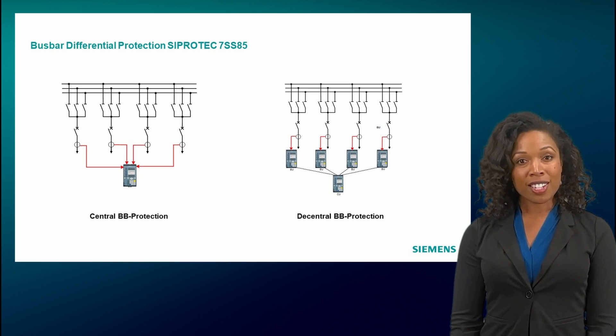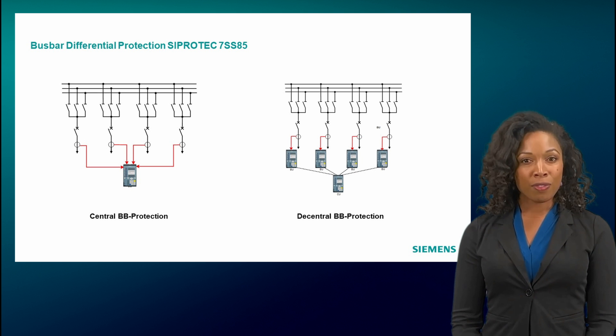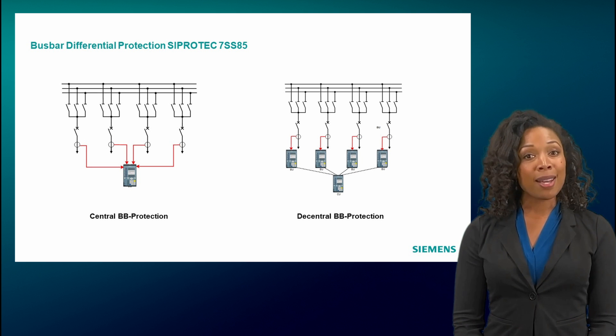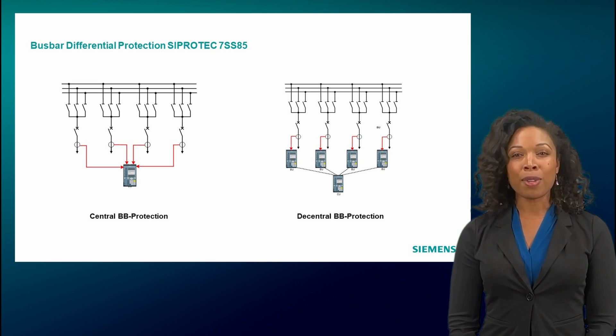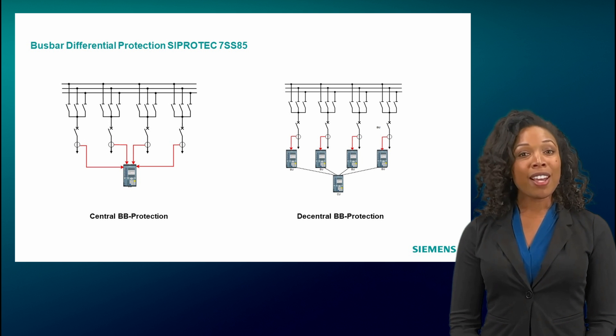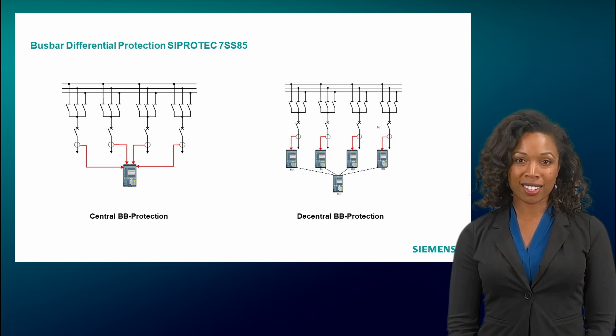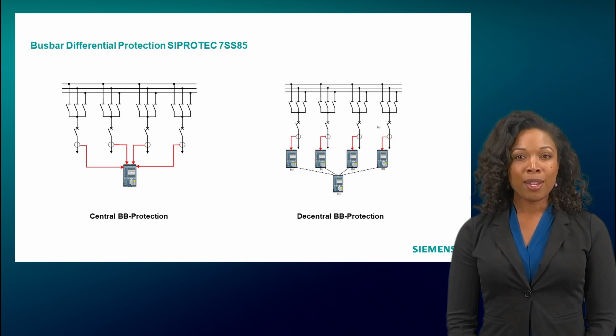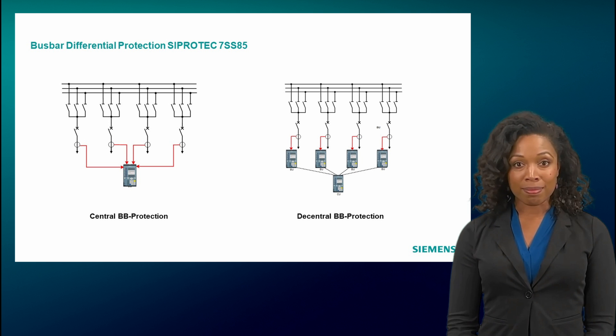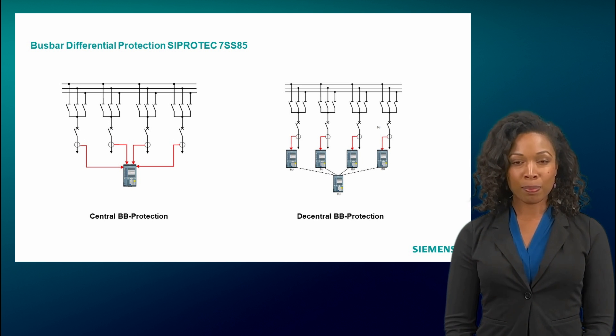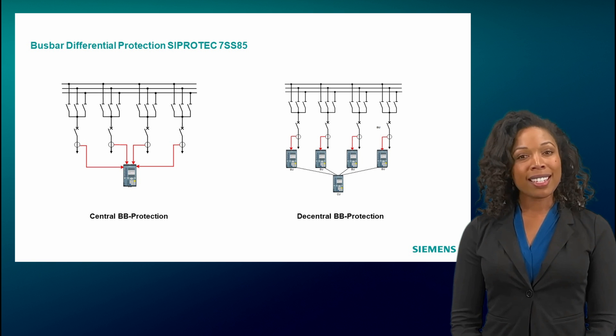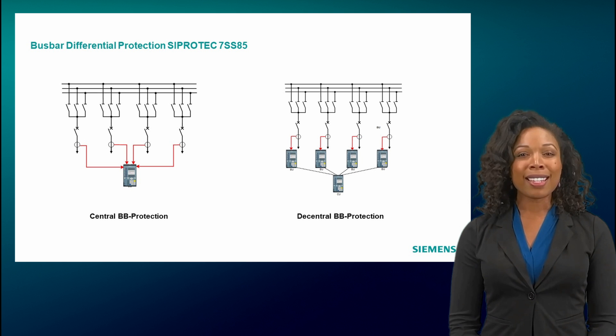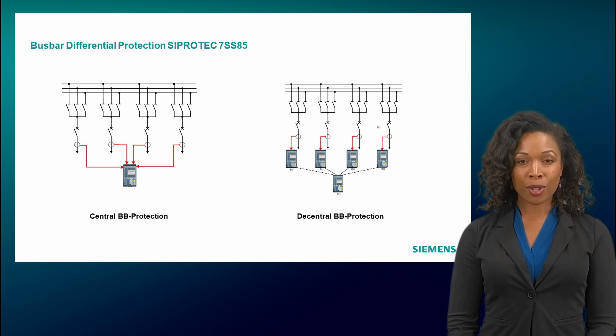Like the differential protection devices already discussed, the 7SS85 busbar protection is based on Kirchhoff's first rule, which states that the sum of all currents at a node must be equal to zero. The node in this case is the busbar. If the busbar consists of several busbar sections, each section again represents its own node, which must be calculated by the busbar protection. This means that for each individual section, the busbar protection must check whether the sum of the incoming currents is equal to the sum of the outgoing currents. The number of possible busbar sections is a selection criterion when determining the configuration.